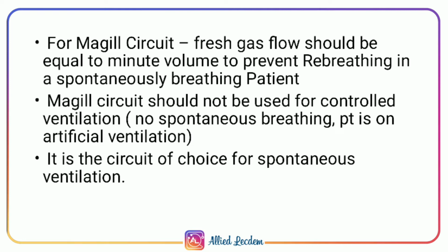If this circuit is used for controlled ventilation, very high flow is required, and in spite of such high flow, prevention of rebreathing is still unpredictable. Therefore, Magill circuit should not be used for controlled ventilation. It is a circuit of choice for spontaneous ventilation. And the APL valve should be near the patient to control rebreathing.